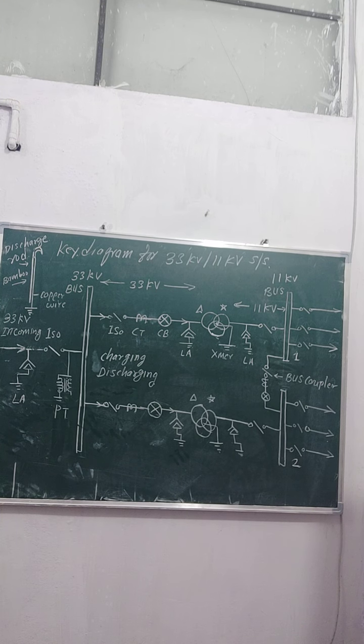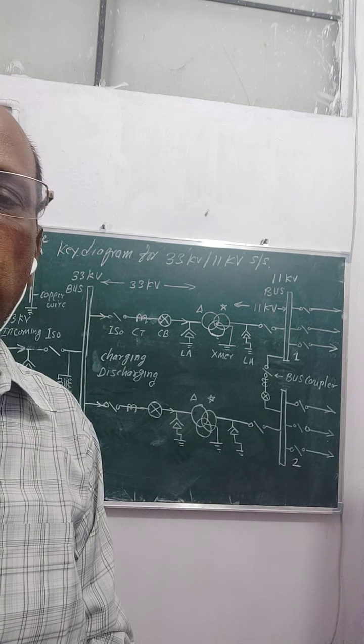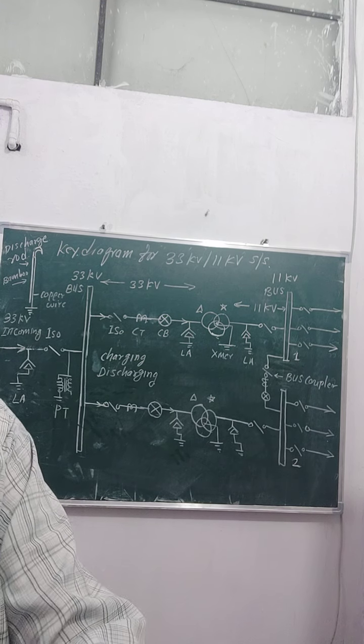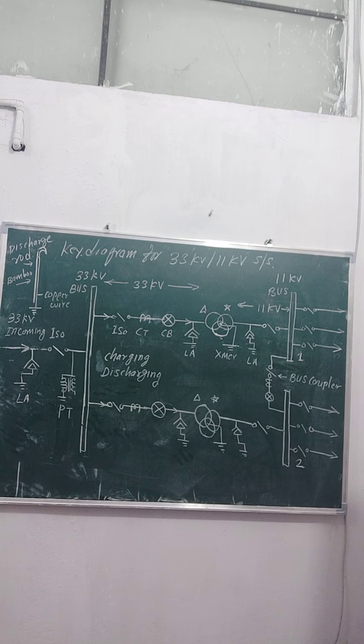So any ground point you can take and this wire is connected to that ground point, and then on the conductor you hang this discharge rod. So whatever charge is available on the conductor or any equipment will go to earth before maintenance. So maintenance becomes easy and there is no danger of any type of shock or return current.